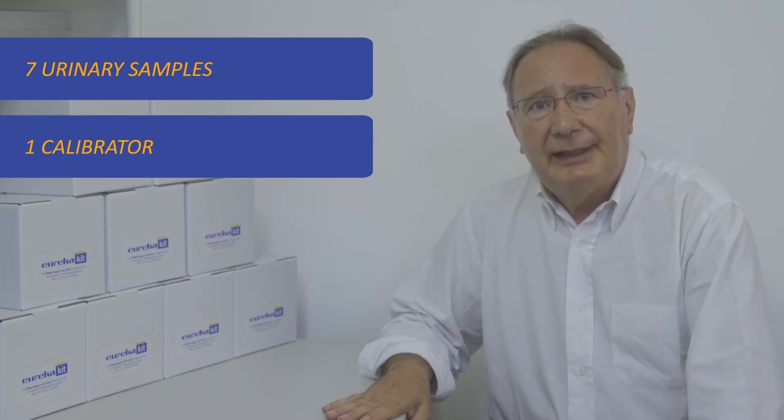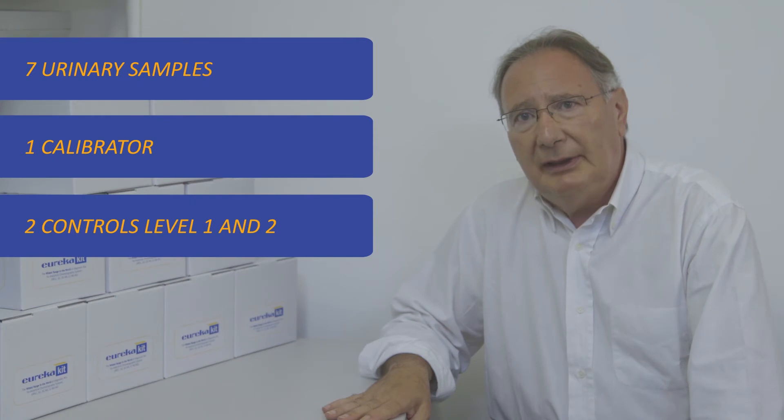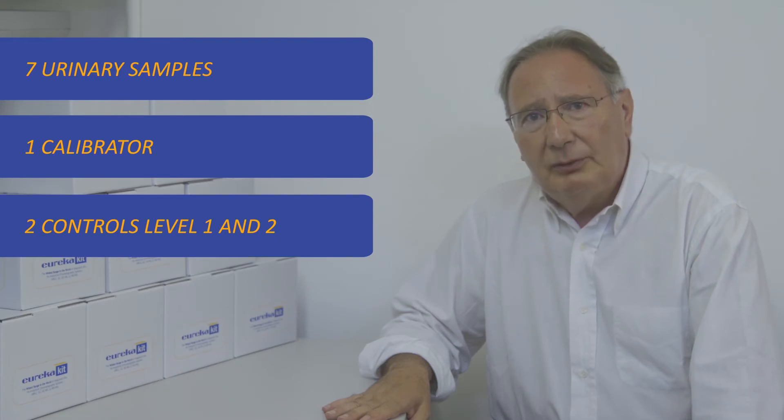We will also analyze two lyophilic controls of level 1 and 2 that will help us to check the validity of the calibration curve and therefore of the entire analytical session.